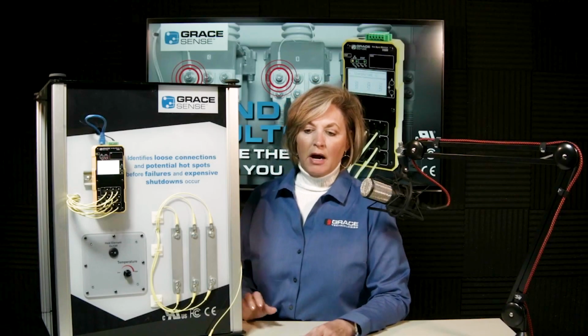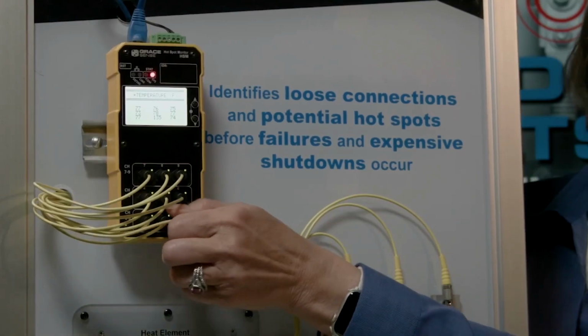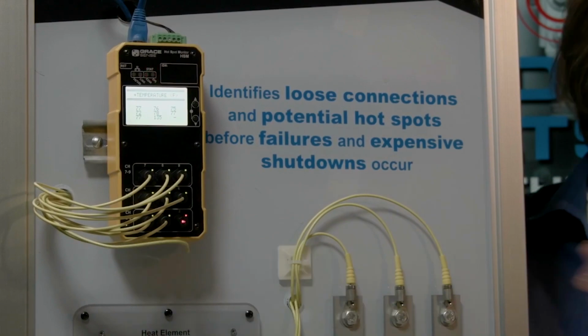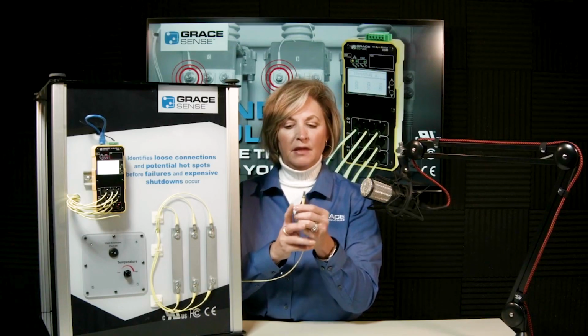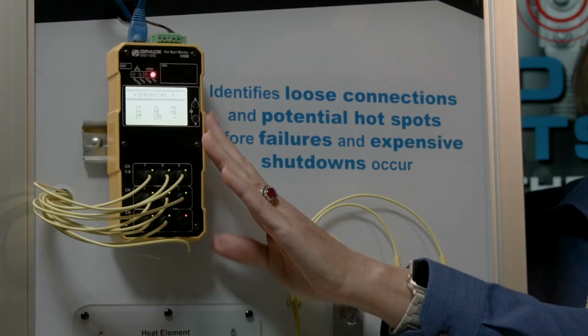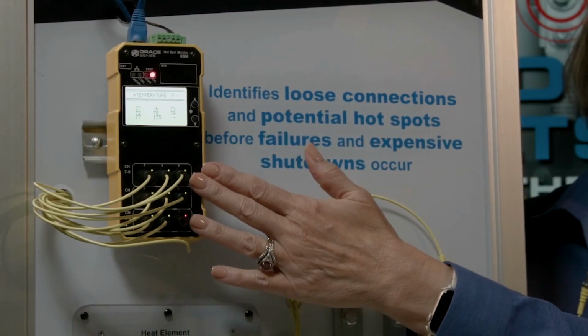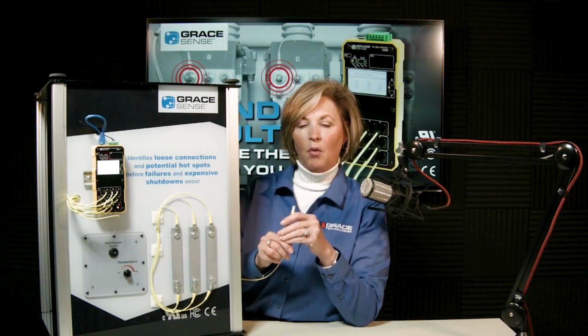So today we're going to talk about Grace's solution for continuous thermal monitoring, and it's called the Hot Spot Monitor, HSM. It consists of a monitor itself and the fiber. This is a direct connect method by which to measure temperature at bolted locations throughout the equipment. So what we do is we pulse an LED light down this polymer fiber, and it reflects off this probe tip. What we watch, and what the sophisticated algorithms in here calculate, is the temperature, by watching the light wave attenuation over time.